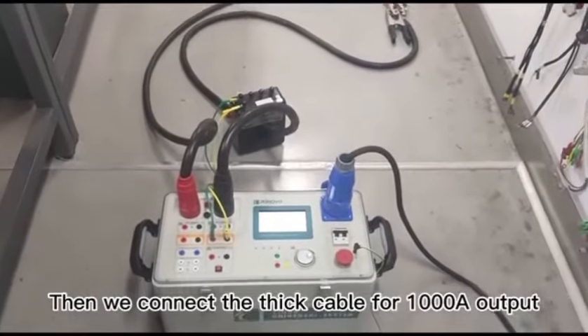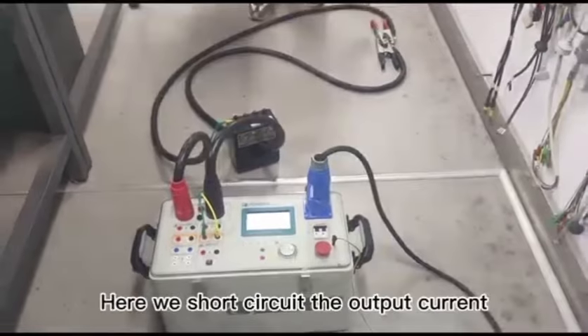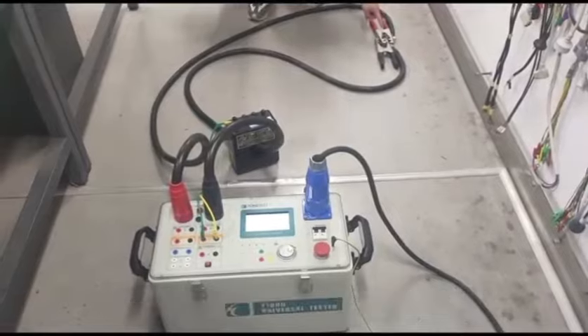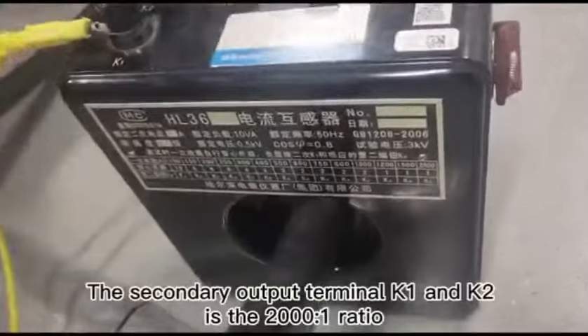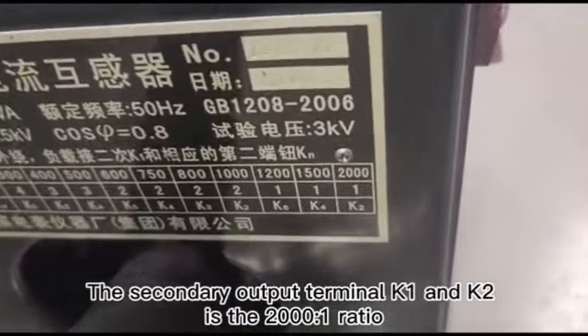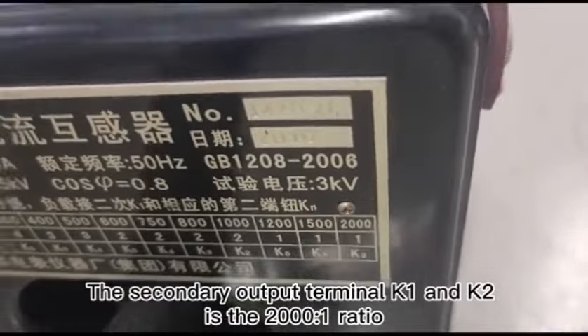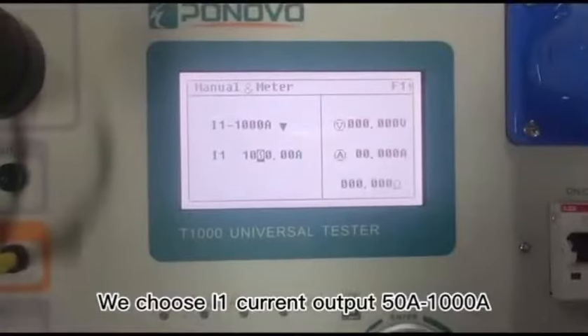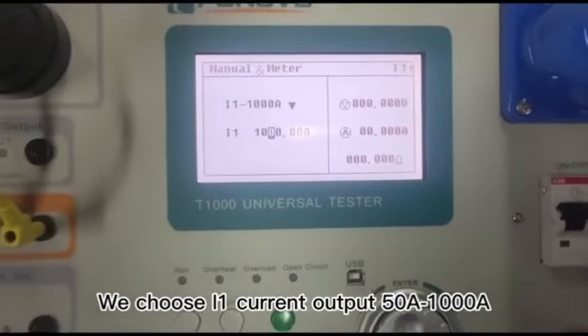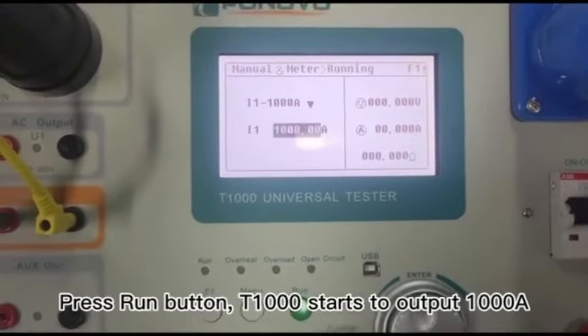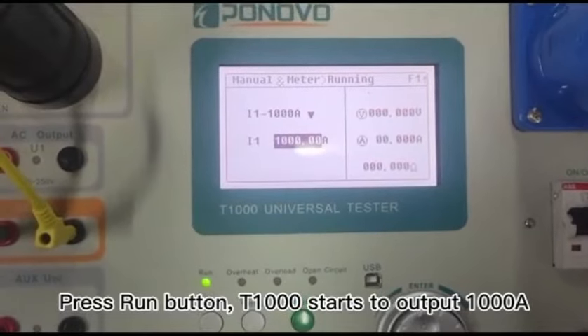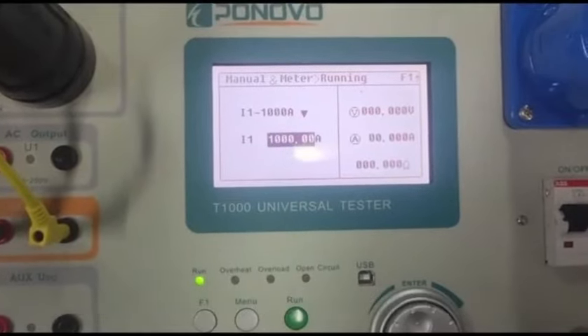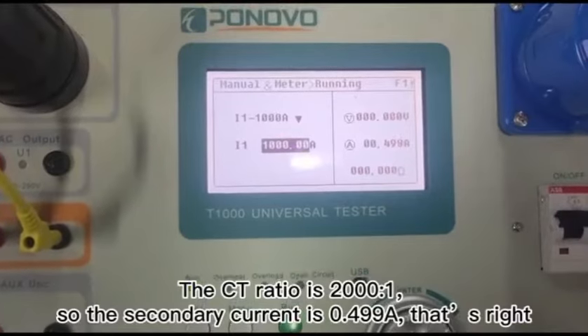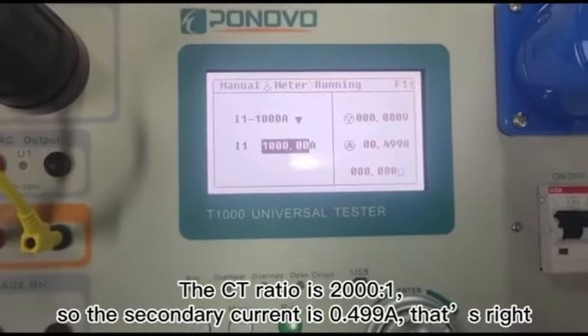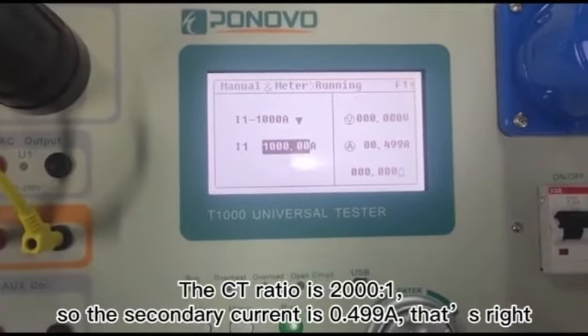that's right. Then we connect the thick cable for 1000 amperes output. Here we short circuit the output current. Here is the current transformer. The secondary output terminal K1 and K2 is the 2000:1 ratio. We choose I1 current output from 50 amperes to 1000 amperes. Press run button, T1000 starts to output 1000 amperes. The current transformer ratio is 2000:1, so the secondary current is 0.499 ampere, that's right.